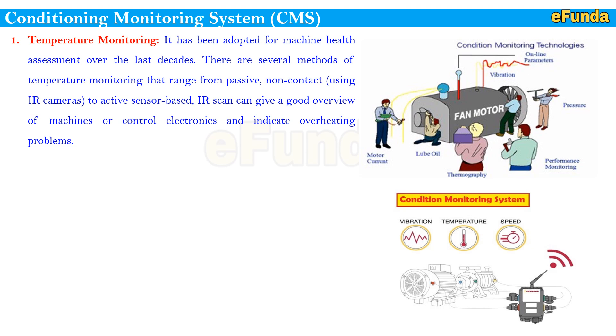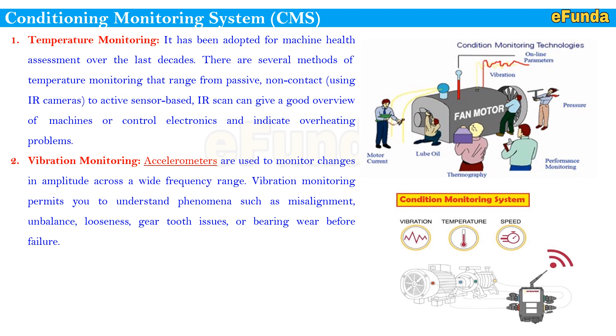Second is vibration monitoring — a very old and most commonly used method for assessment of machine condition. It helps detect failures and understand their root causes. Mainly accelerometers are used to monitor changes in amplitude across a wide range of frequencies. Vibration monitoring permits you to understand phenomena such as misalignment, unbalance, looseness, gear tooth issues, or bearing wear before failure.